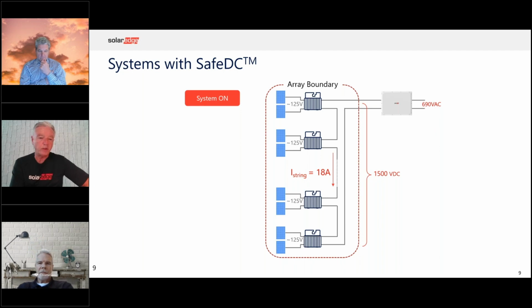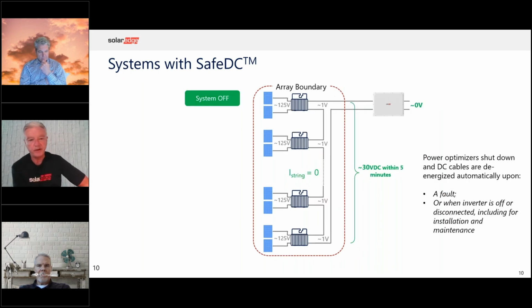So when it's normally operating, that's a 1500 volt DC circuit. But in the safe DC mode, which is the next screen there, yeah. So you'll see when the system is off that there's only 1 volt coming out of each optimizer. So in this case, if you have 30 optimizers in a string with 2 modules connected to each of those, that's 60 modules altogether. Each optimizer will only be putting out 1 volt. And so if you put a multimeter on that string, you'd only see 30 volts DC.